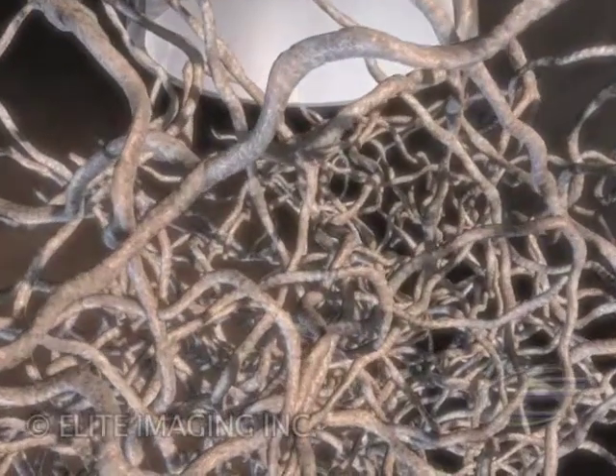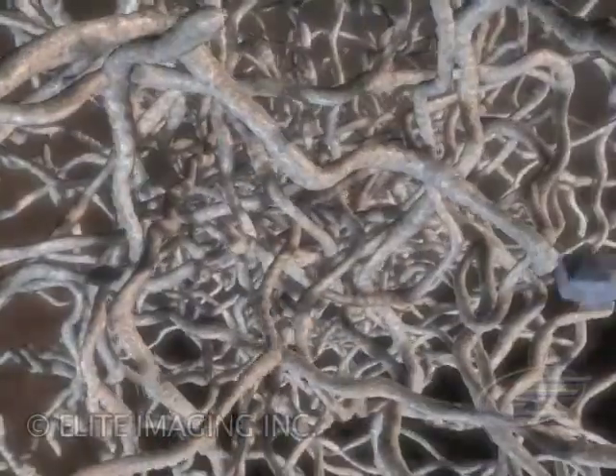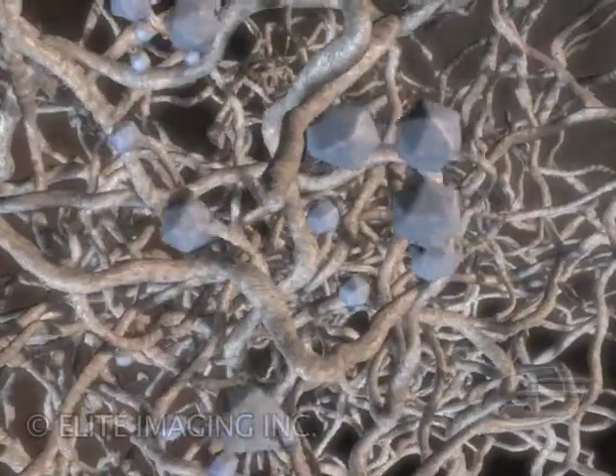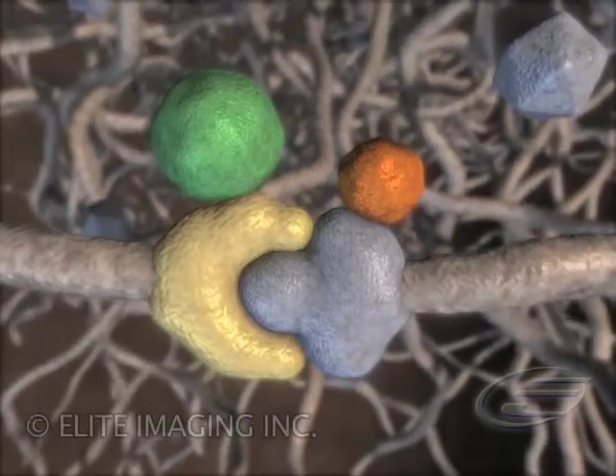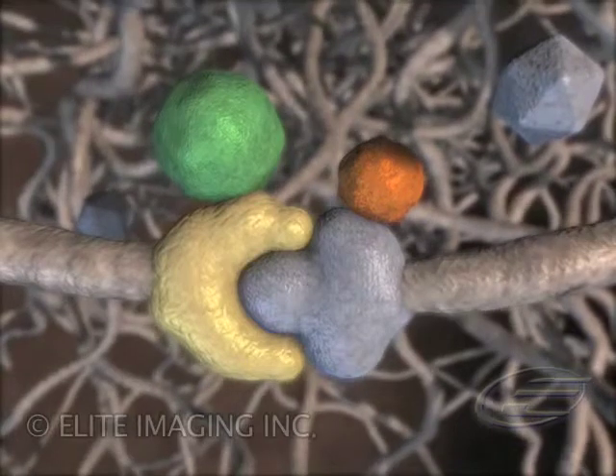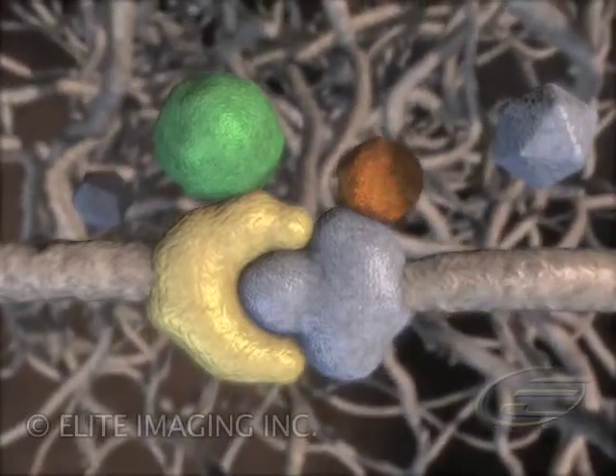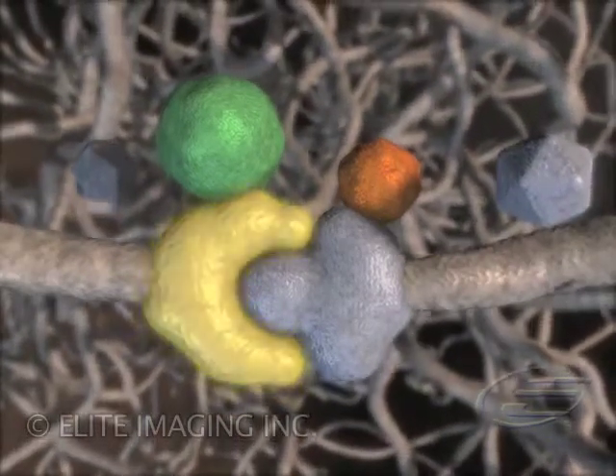It is photopolymerized onto the end of the optical fiber from a precursor solution of polyethylene glycol, a biocompatible hydrogel that allows analytes such as glucose to diffuse freely through it. Bound into this matrix are two different assay molecules that can bind to each other but can be displaced by the analyte depending on its concentration. For glucose, we use concanavalin A and betacyclodextrin.